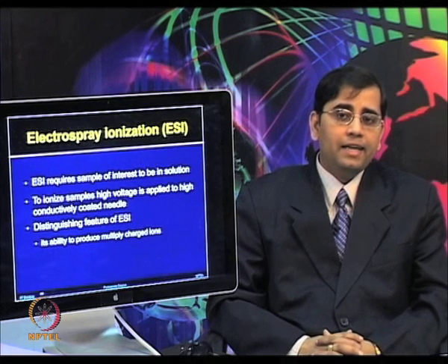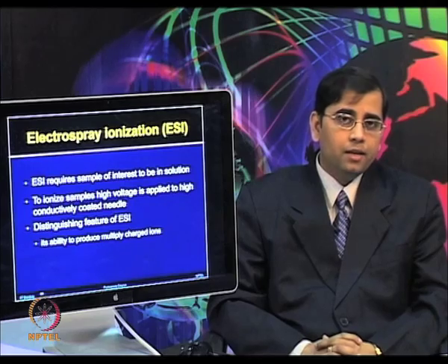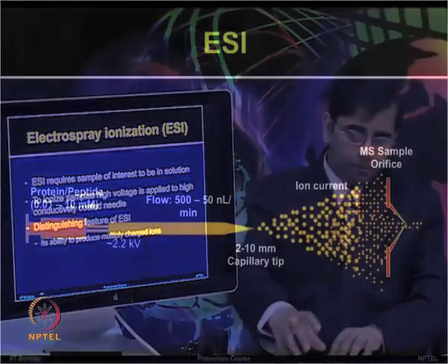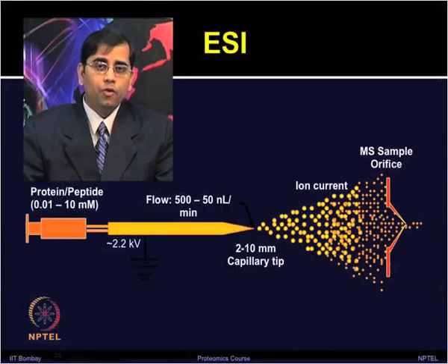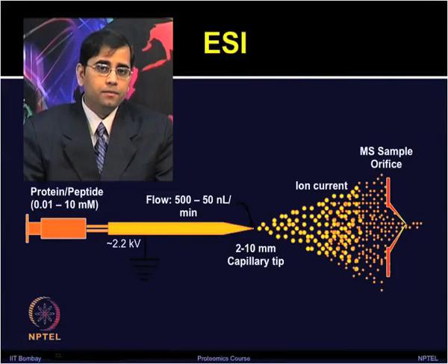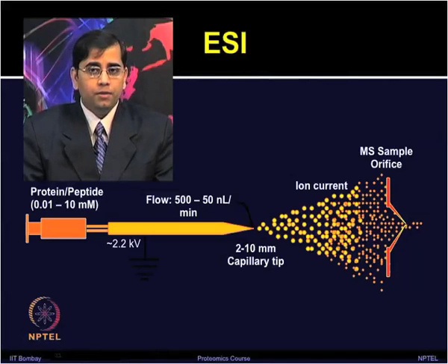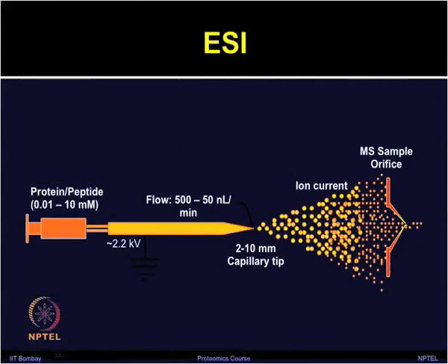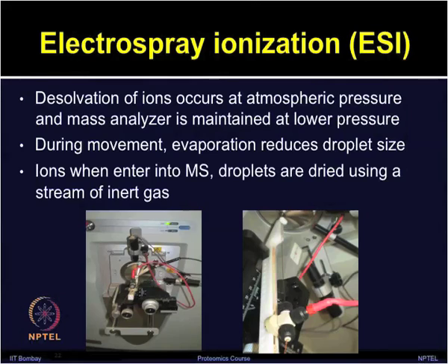Here you can get an overview of the process involved in electrospray ionization. Small droplets of solution are generated by the Taylor cone, which contains the peptide analyte. Protons from the acidic solution provide the droplets with a positive charge, so they can move from the needle to the negatively charged instrument. In ESI, the desolvation of ions occurs at atmospheric pressure, and the mass analyzer is maintained at lower pressure so that ions can be drawn into the MS based on the pressure differential.